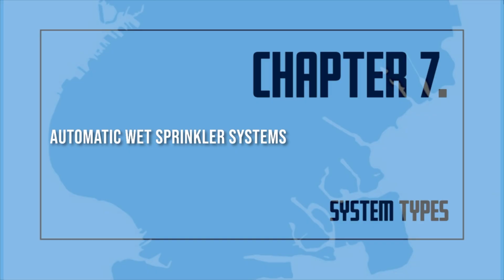sprinkler heads. The sprinkler heads are normally closed by a disc or cap. This cap is held in place by a heat-sensitive releasing element. A rise in temperature to a predetermined level causes the sprinkler head to open. Water is then discharged in the form of spray. When the sprinkler heads open, they are said to have fused. The sprinkler heads are fitted at standard intervals on the piping. If more than one head opens, the area sprayed by each overlaps that of the sprinkler head next to it.